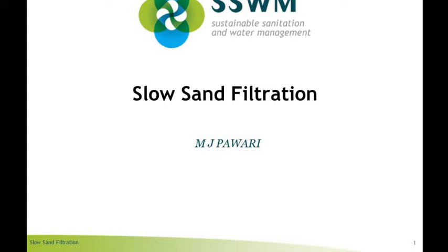The next one is the filter media of sand, which is used for the filtration of water at the top of the gravel. Okay, and the depth of that sand layer varies from 600 mm to 900 mm.